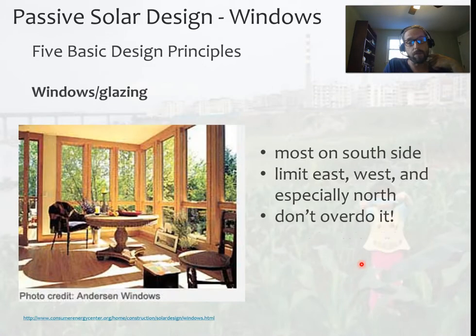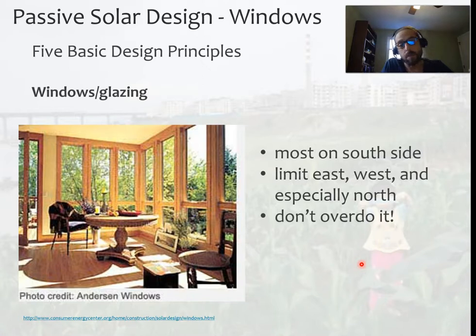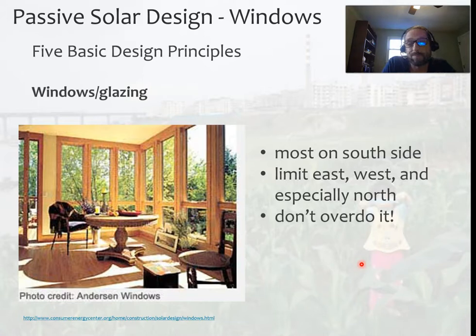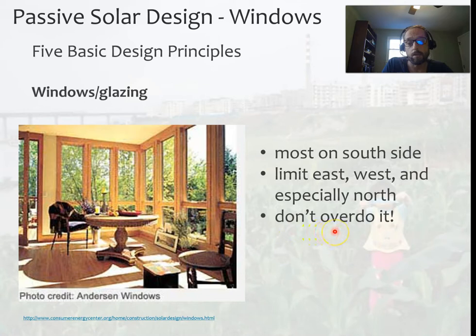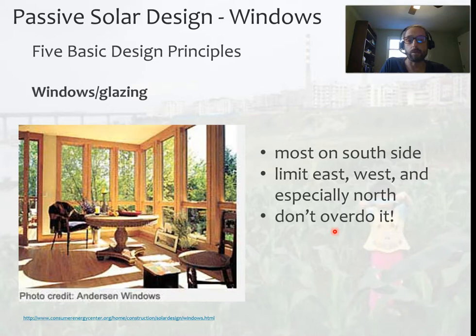You need to combine orientation with windows, or glazing. It's not really helpful to have the sun hitting the south part of your building if you don't have windows to allow that sun through and use it inside the building. If it's hitting the wall, it's warming the wall and might slowly heat the house, but you really want enough windows to allow sunlight in when you want it, so it can come in and heat the building. However, you have to be careful — you don't want to overdo it. You don't want a building full of windows because windows have really poor R-values, so you can't have a really efficient building with a lot of windows. The maximum you can achieve is around R-8 to R-10, and those are incredibly expensive windows.